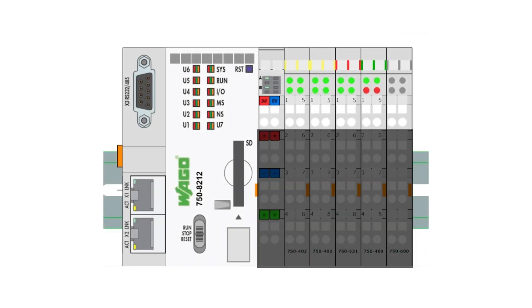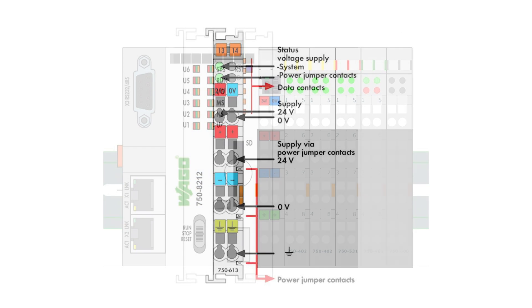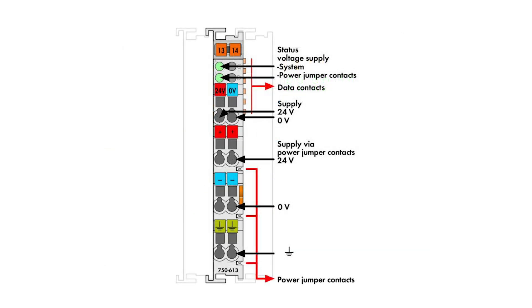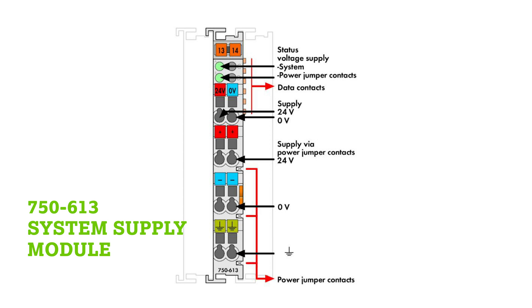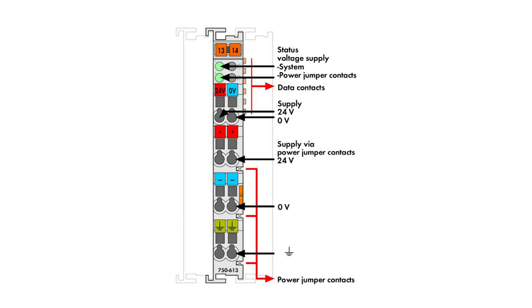First, we have system power. The head unit requires a 24 volt DC power supply. This powers the unit and provides system power, which is 5 volts DC, to the internal electronics of the other I.O. modules in the node. If the internal current demand exceeds the set value for the PLC or coupler, an additional supply module is necessary — that part number is the 750-613.